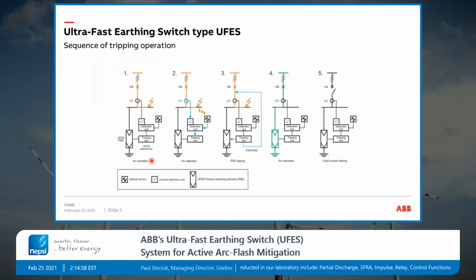And then what we have here is, number one, let's say, an internal arc happening here, let's assume on the bus bar. And we have this internal arc burning. So first of all, in step number 2, we are detecting by light. Here you have the symbol of a light sensor. And we are detecting by current. We do recommend to have this logical AND connected, means we are detecting an internal arc with light and current.